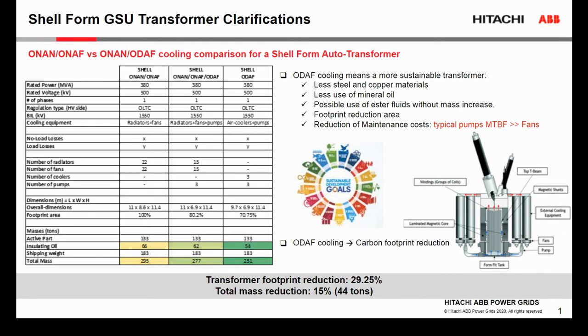And here is a comparison of how we can change the cooling system on the shell transformer, and how we can change the size of the transformer and oil volume by changing the type of cooling. You can see that with the same load losses and no-load losses, we can significantly reduce the oil volume and the total weight of the transformer. This is the same design of the active part, but the type of cooling system is different. In the third column, we see the transformer with ODAF cooling only, and the total weight of the transformer can be reduced by 44 tons.